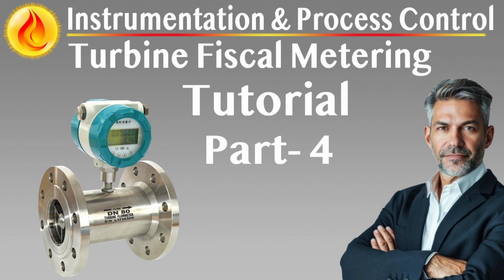The prover microcomputer must control all relevant field equipment, including stream flow control valves, prover four-way diverter valves, and isolation valves. It must monitor valve seal status, position feedback, and detector switch health. In the event of any valve misalignment, leakage, or failed sensor, the system must abort the proving sequence, initiate alarms, and prevent further proving until the issue is resolved.